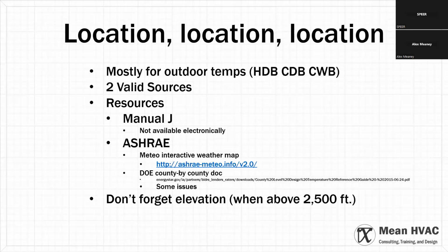Didn't even put it in my notes because it's so important and I just assumed I would remember. When using ASHRAE data, there are different data sets. They break their numbers down by mean extreme, 0.4%, 1%, and 2% for cooling, and 99%, 99.6%, and mean extreme on heating. Those options are meant for commercial designers to be making choices there. In a residential design, you shouldn't have the choice. You're not supposed to have the choice. You're supposed to use 1% for cooling, 99% for heating. And the same is true for that peak dehu, 1% for peak dehumidification is the standard. Some people advocate 2%. I mean, if they're going to go lower, that's fine. But 1% cooling data, 99% heating data, those are the requirements.